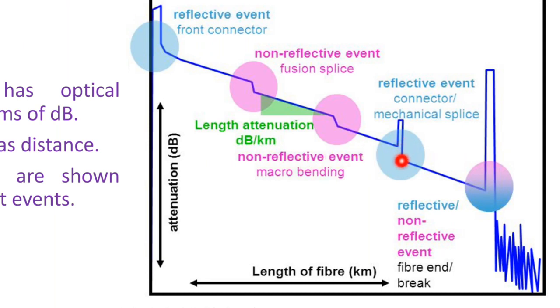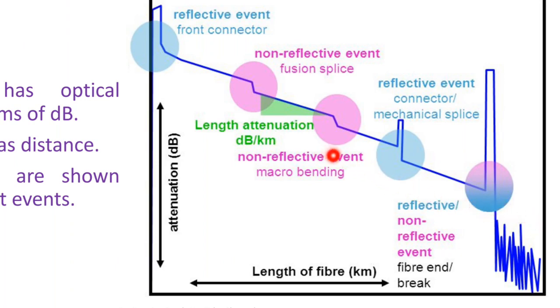Moving further, there is a big abrupt change indicating a reflective event due to a connector or mechanical splice. Then a very big slope change indicates a fiber break. When a fiber break occurs, you cannot have proper data for further distances. This is how we trace data with respect to distance using the reflected signal. In OTDR, we use the reflected signal and based on how much reflection is happening we identify what type of fault is occurring in the optical fiber.